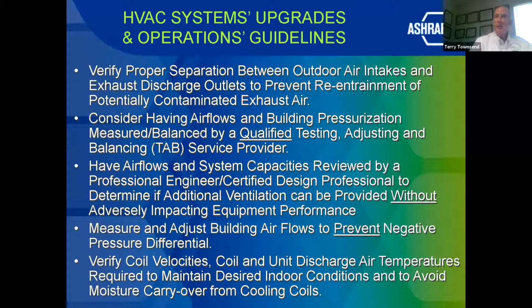This is somebody that is certified by NEBB or by AABC or TABB. Have airflows and system capacities reviewed by a professional engineer or certified design professional, and make sure that what you are adjusting will not impact the equipment performance. Measure and adjust building airflows to prevent negative pressure differential. It doesn't matter where you are, north or south, you want to have positive pressure in the building. And then verify the coil velocities and unit discharge air temperatures to avoid moisture carryover.